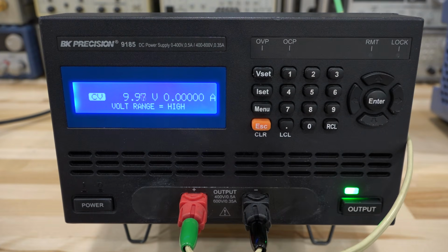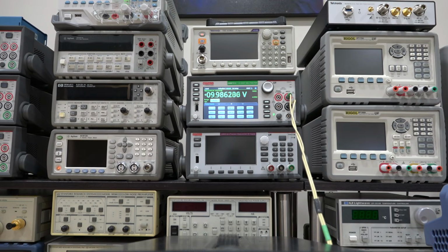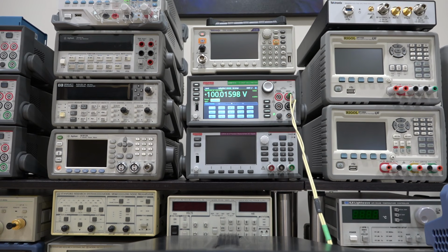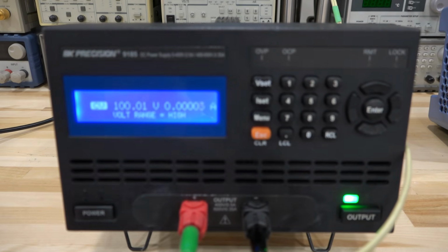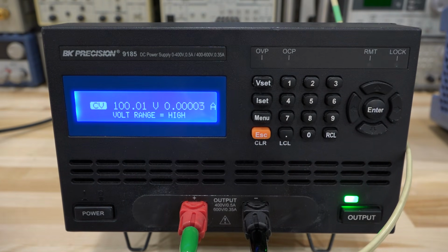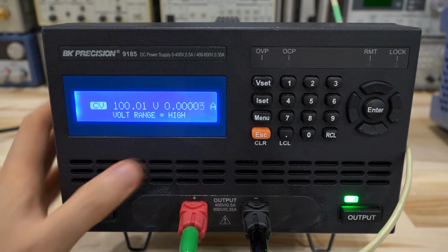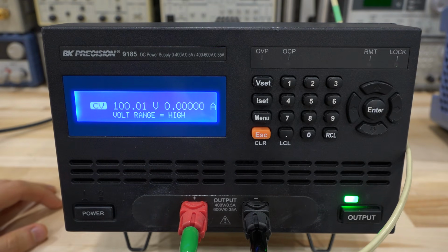Here, 10 volts is measuring 9.97 on the instrument, and on the meter our 10 volts is reading 9.986, so it's actually really close to what it's supposed to be. It's just a tiny bit off. So let's set some other voltages. Let's set the voltage to 100 volts, and here's 100 volts, and that's not bad at all. We're only off by 10 millivolts there, and in fact the measurement on the instrument also jumps back and forth on the smallest digit, so it's actually matching what we're measuring. So the question is, do we want to calibrate it such that the reading is closer to what it's supposed to be? It wouldn't hurt going through the calibration procedure.